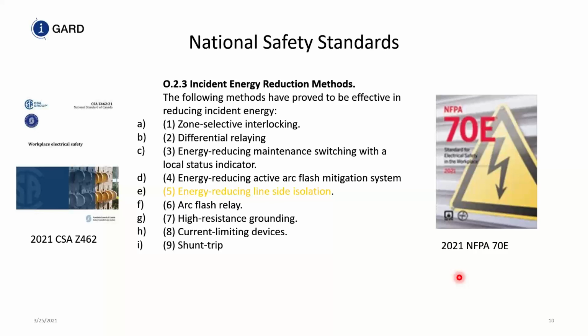Zone selective interlocking, differential relaying, energy reducing maintenance switch with a local status indicator, energy reducing active arc flash mitigation system. This is a new one this year, energy reducing line side isolation. And this is new for both NFPA 70E and Z462. So what it does is it includes another barrier between the line and the load side of your main incoming breaker. Arc flash relay, high resistance grounding, current limiting devices, and shunt trip.